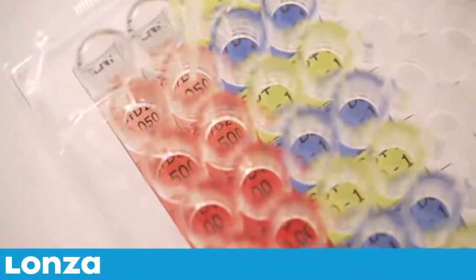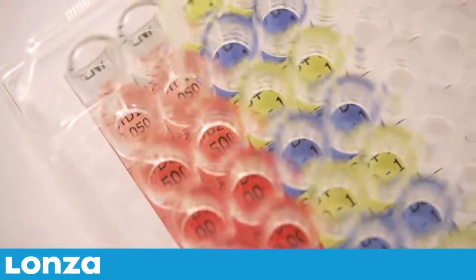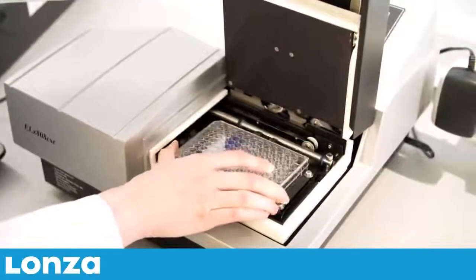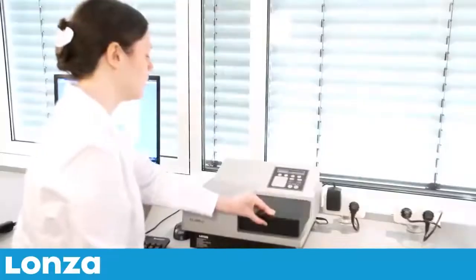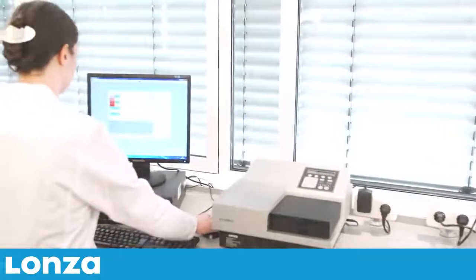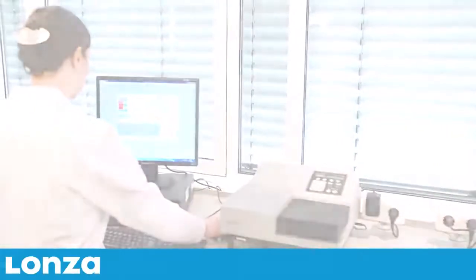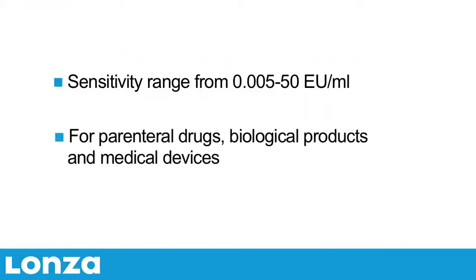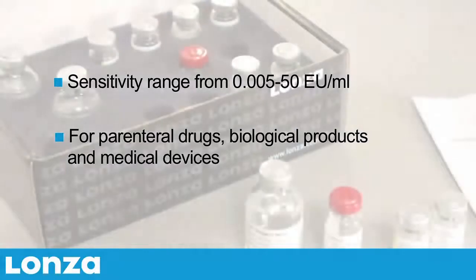A test sample is mixed with the LAL reagent, incubated in a reader and automatically monitored over time for a change in absorbance. This assay has a sensitivity range of 0.005 to 50 EU per mL, and it is well suited to in-process and final product testing of human and animal parenteral drugs, biological products and medical devices.